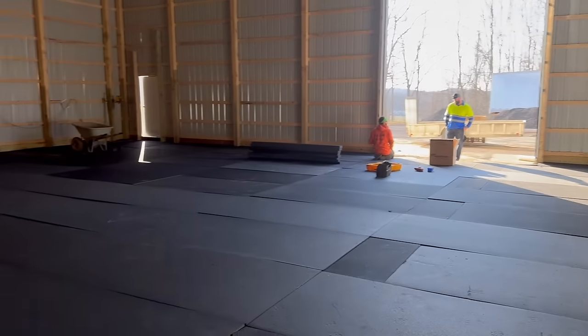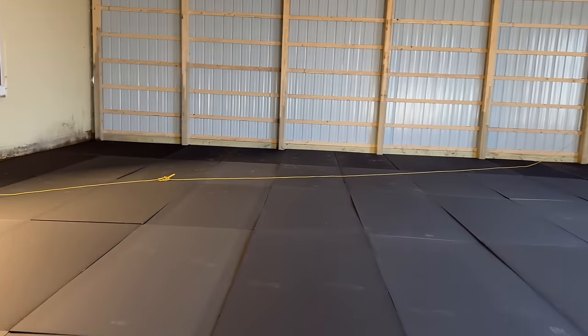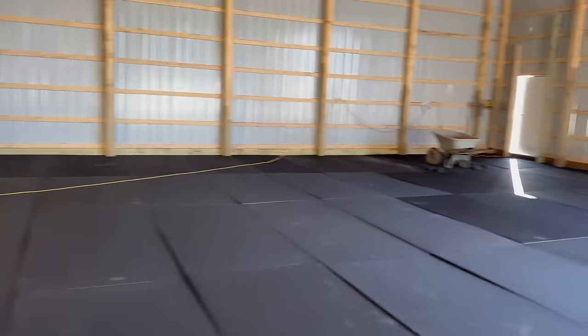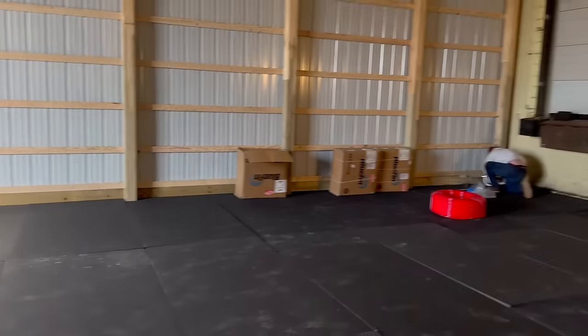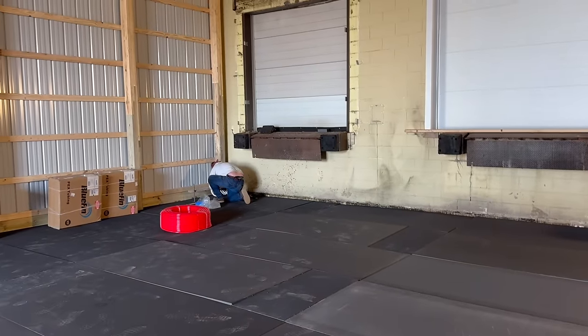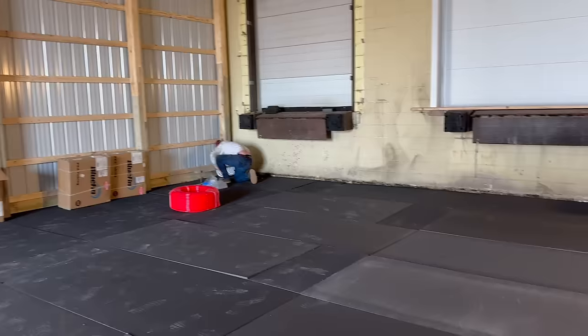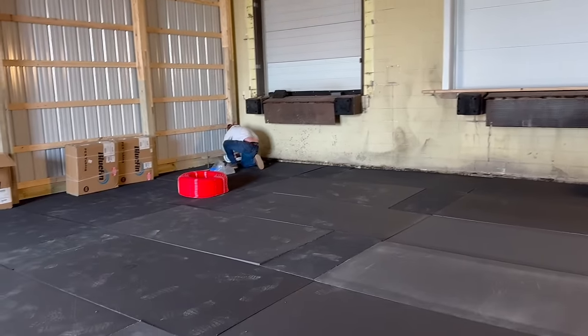We're gonna be running 500 foot loops in this barn, which we've done a bunch of times. Some people say you can only run 300 foot, but we've done, I don't know, probably 20 or 30 barns at 500 feet and it works really good. You just need a little bit stronger pump. So we use a Taco 009 pump or a 3-speed Taco pump and that works great for 500 foot loops.